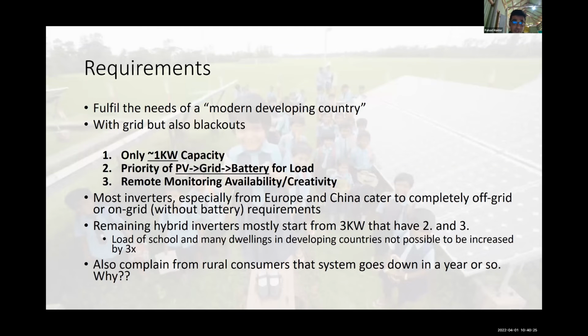It also has priority of PV first, then the grid, then the battery. So when solar is available, the load uses the PV, then the grid, then the battery. If you don't have the grid, it goes to the battery. This also discourages excessive discharge from the battery, which causes degradation.